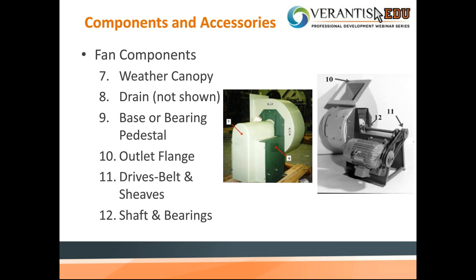So we've got a few more components. Number 7 is the canopy. This is a weather canopy, and like I said, it captures both the belt and pulley and motor system, as well as the fan shaft. What we don't see in here is a drain. Most fans come with a drain. So if there's any built up moisture inside the housing, it has a place to go, and your fan isn't treated like a pump. The water can actually go out somewhere.